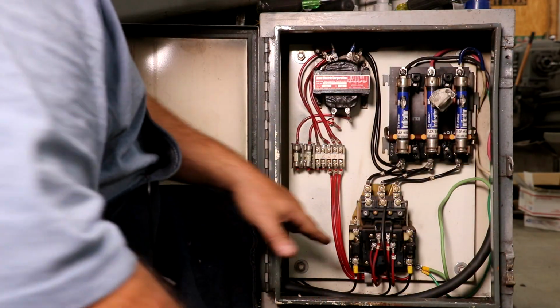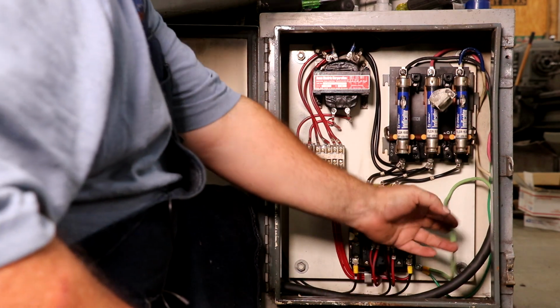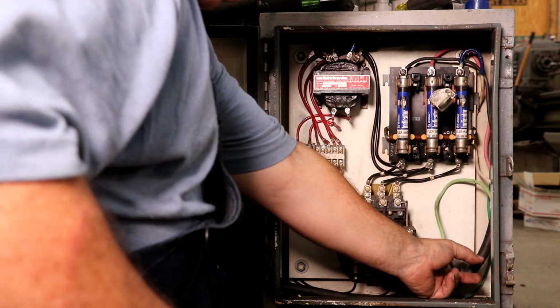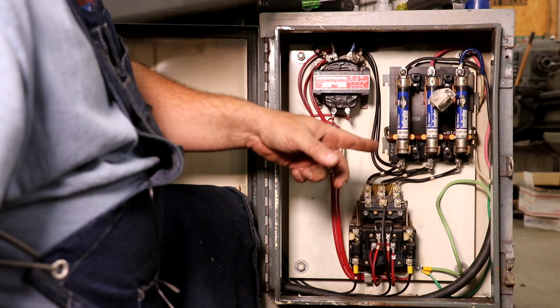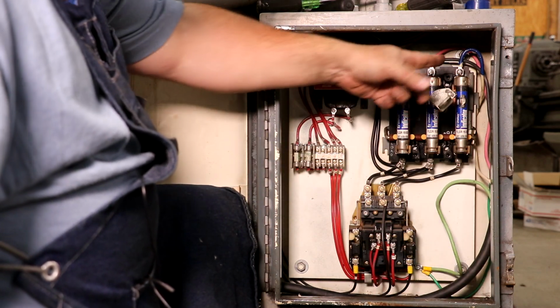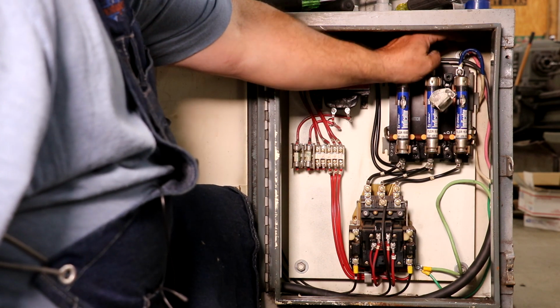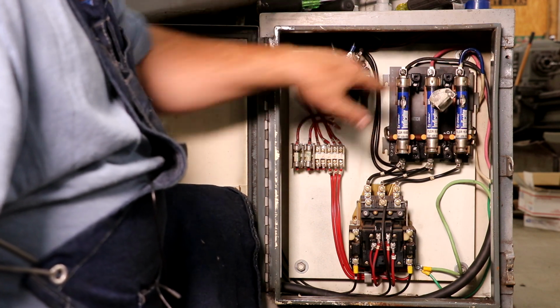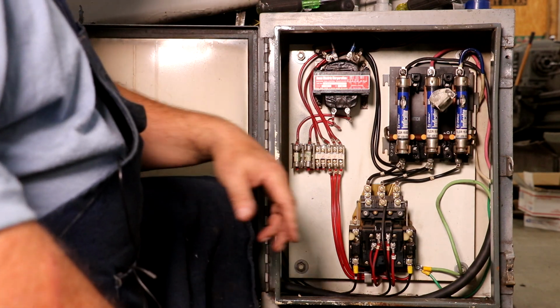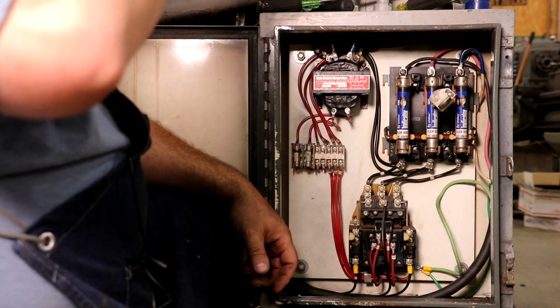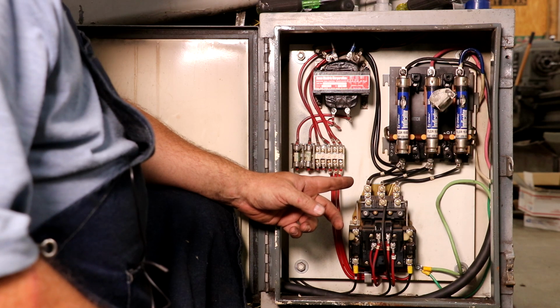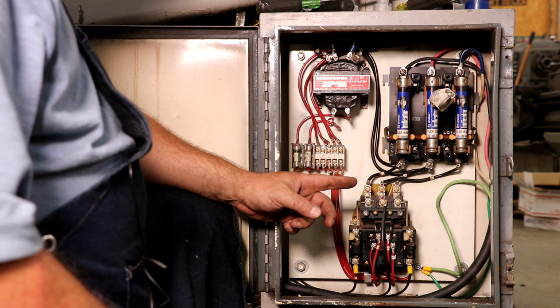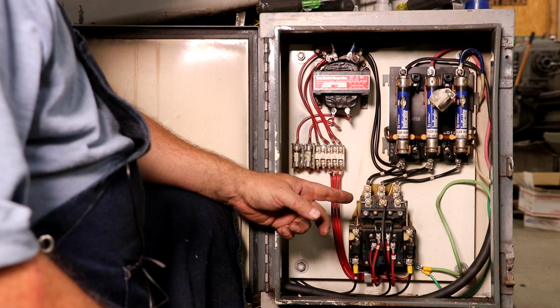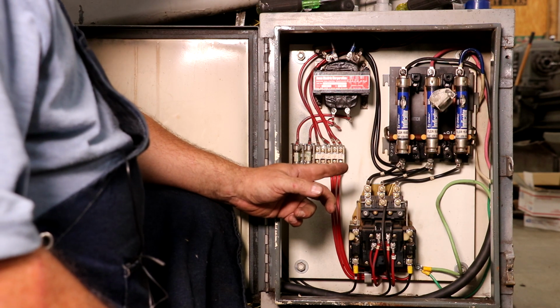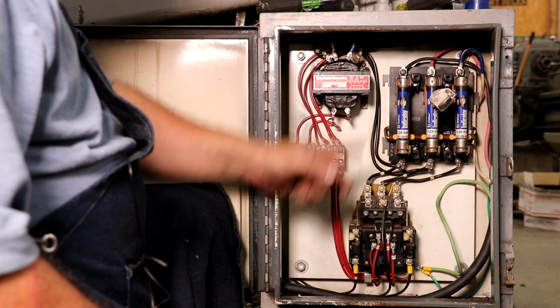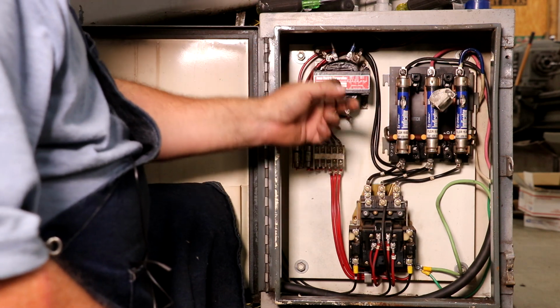So just showing what we've done here - here's our input line coming in. Notice I have my ground tied into the ground bus down here, and up on top of the fuse block we have our 3 hot wires coming in. I took blue electrical tape and turned that one blue, plus red and black. One thing I'm paying attention to is that because I'm running on a rotary phase converter, 2 of my legs stay hot, whereas the 3rd leg is only hot when the phase converter is on. I've made sure I've got my 2 lines that are always hot tied into the lines here that go to the transformer.